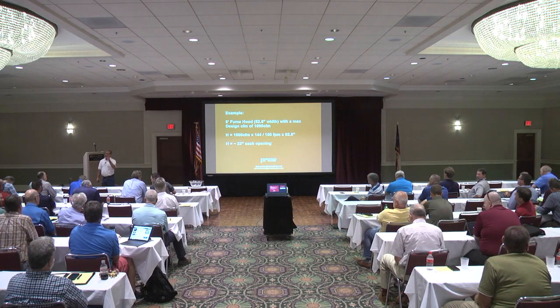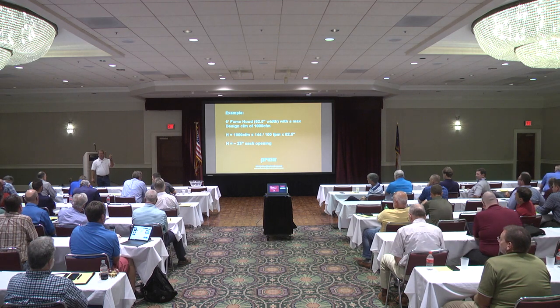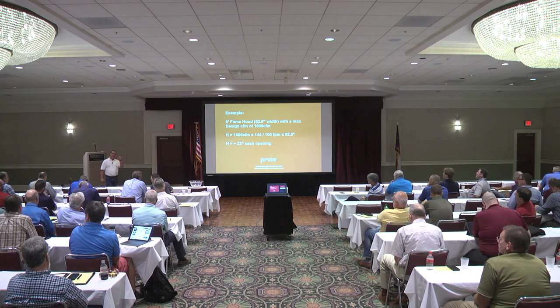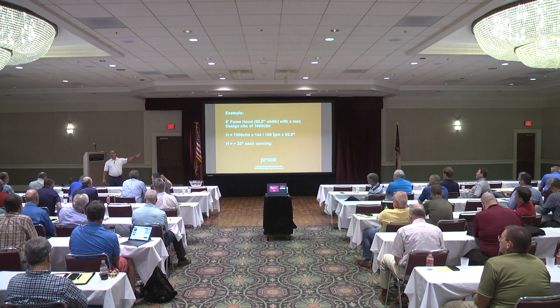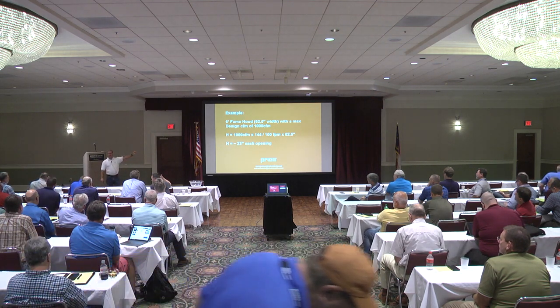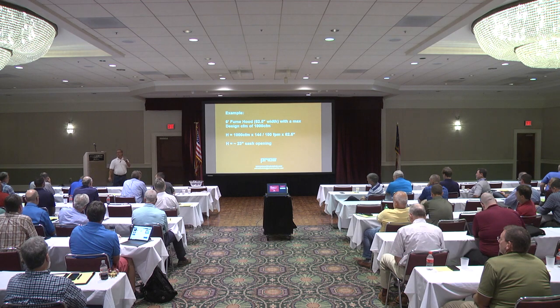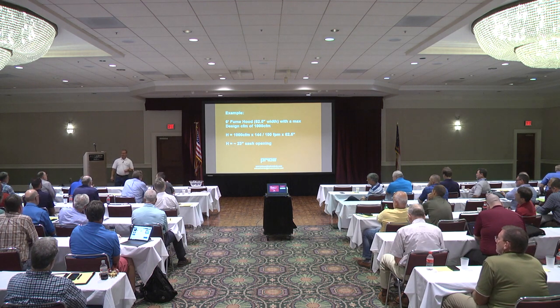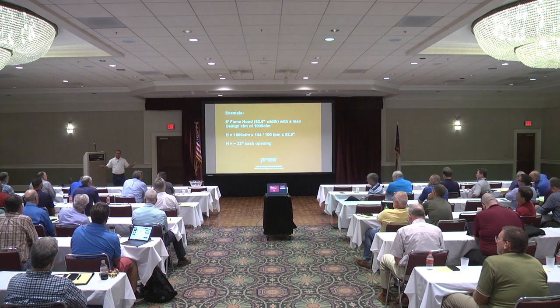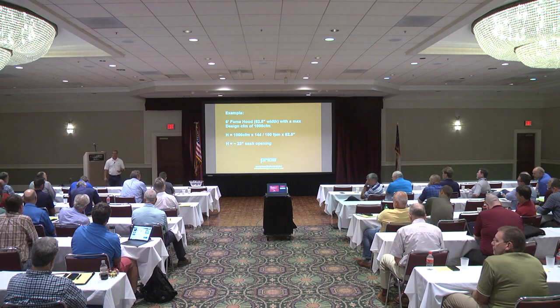So on the fume hood monitor, you'll have an emergency button that will drive the valve to its maximum design CFM, 1,000, regardless of the sash position. So back to this gentleman here, when he said, I want 125 feet at 18 inches, if you push the emergency button, you'd probably get that. But I'm trying not to override things. Most people want to test the project based on automatic operating modes. I mean, that's what we're going to deliver.